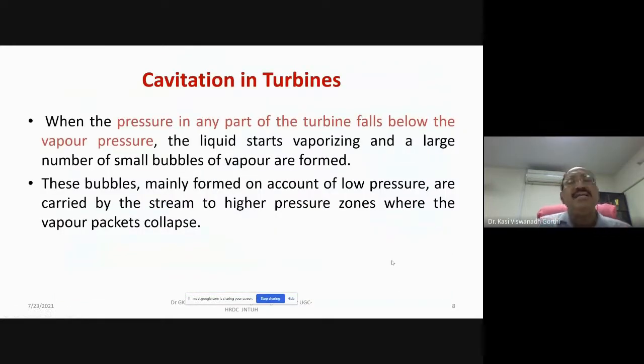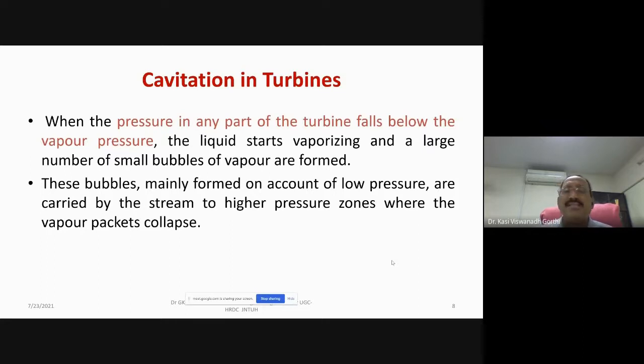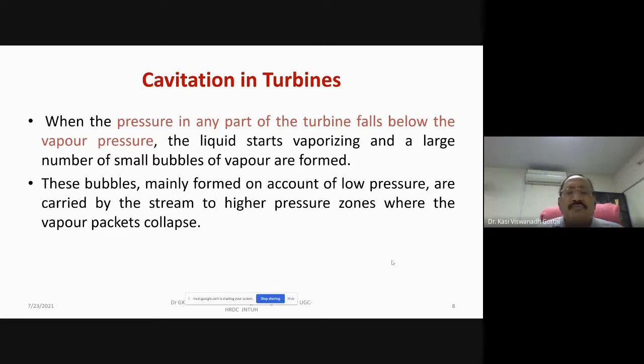The next topic is cavitation in turbines. Where does this cavitation occur, and is it a desirable phenomenon? When the pressure in any part of the turbine falls below the vapour pressure, the liquid starts vaporizing and a large number of small bubbles of vapour are formed. This happens because of the fluid property — vapour pressure. For a flowing fluid, at any section where the pressure is dropping below the vapour pressure, there will naturally be vaporization.